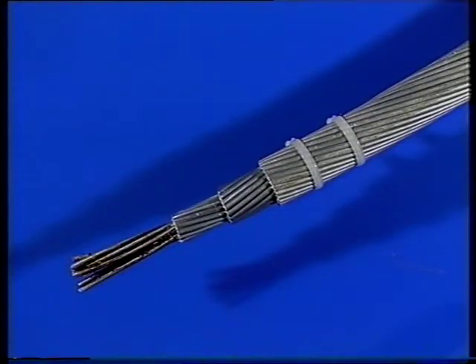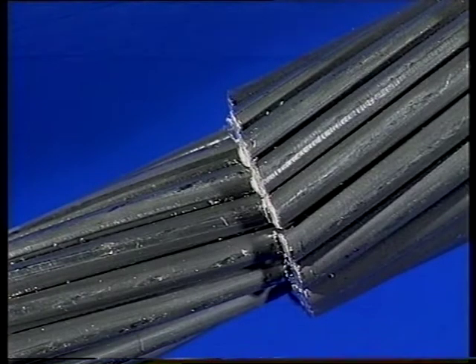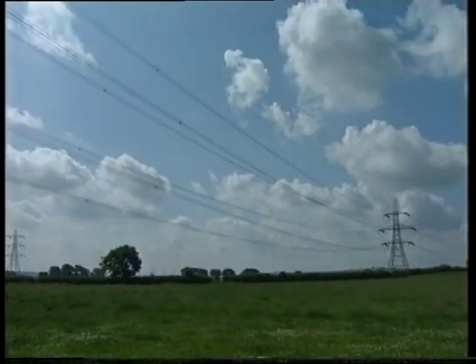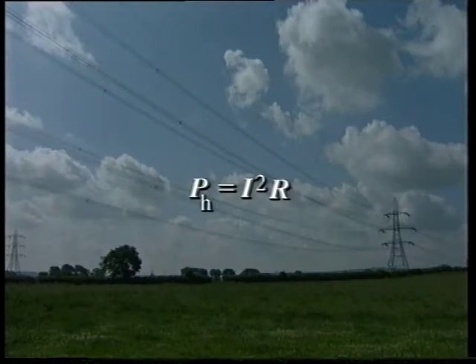So, the bigger the cable, the lower the heat loss, but at a price. Cable design, then, is as much to do with economics as it is with material science. I said earlier that the reason for trying to minimize R was to keep power losses in the cable low. If we can reduce I, then the saving will be very large indeed, because I is squared in this expression.